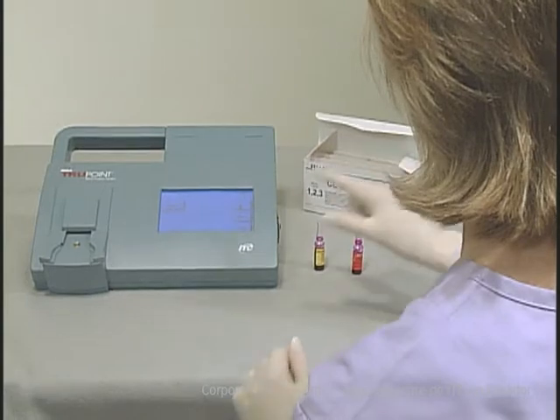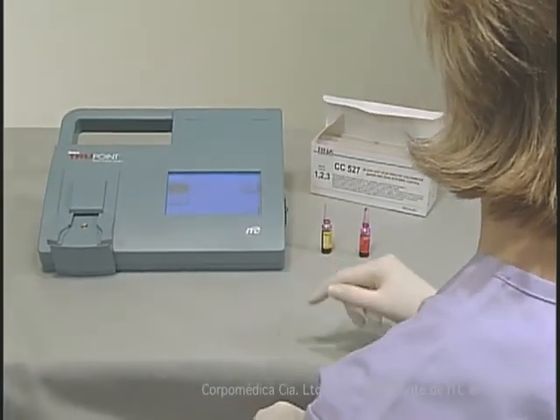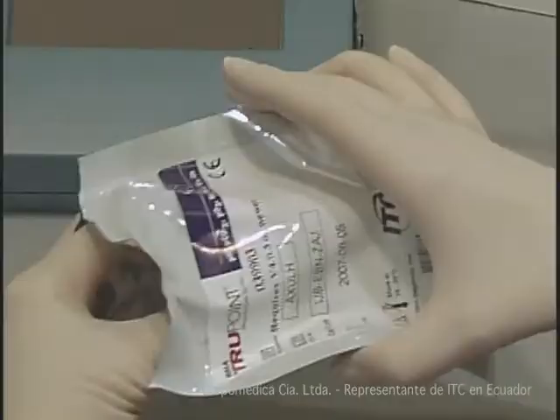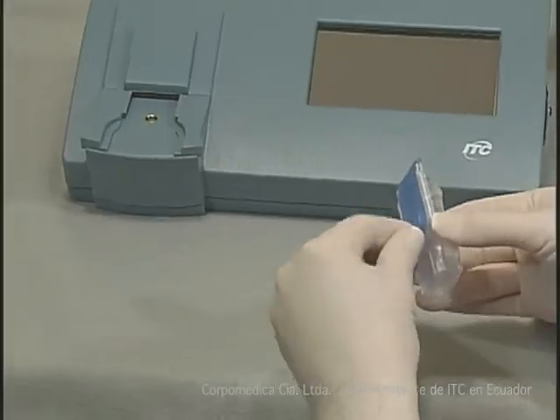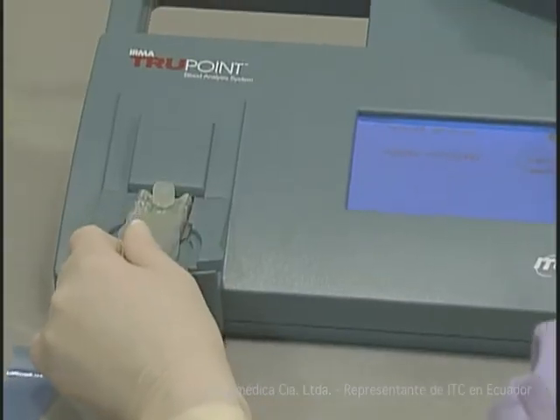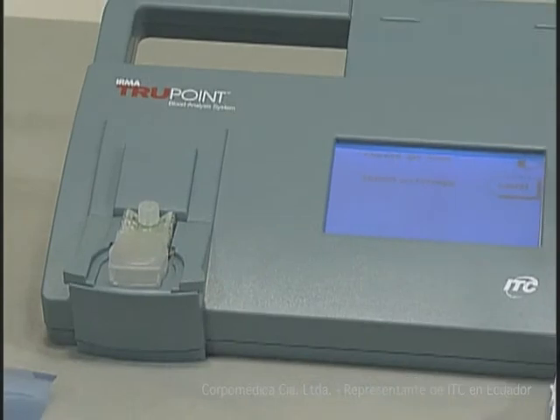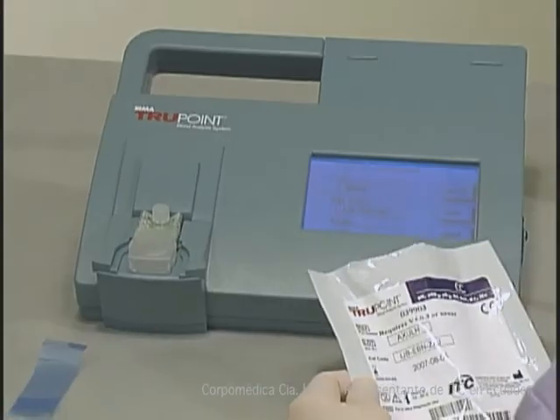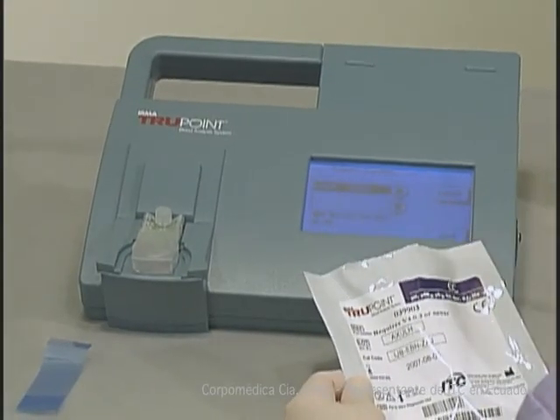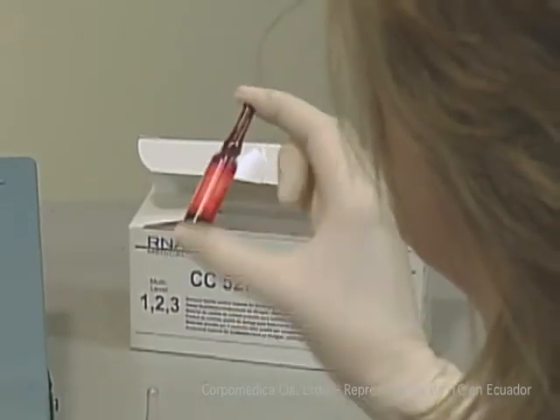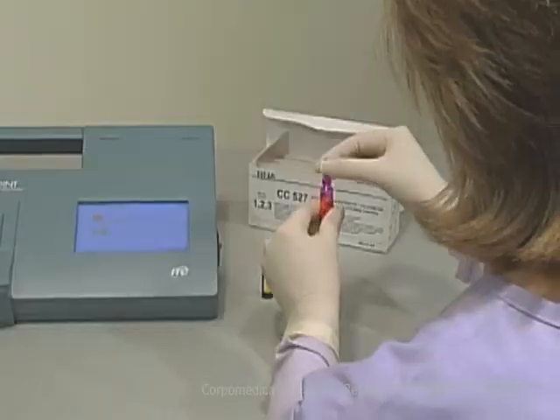From the main menu, press QC Test. Press Liquid. Select the product type to be tested. Open the cartridge pouch and insert the cartridge into the analyzer. Verify the lot number and calibration code and press Next. Then, select the control to be tested and press Next. Next, shake the control for approximately 10 seconds and set the control down.